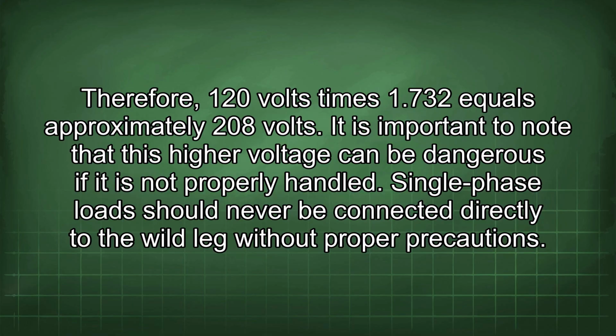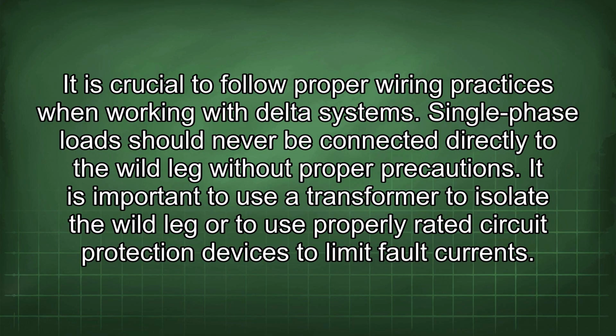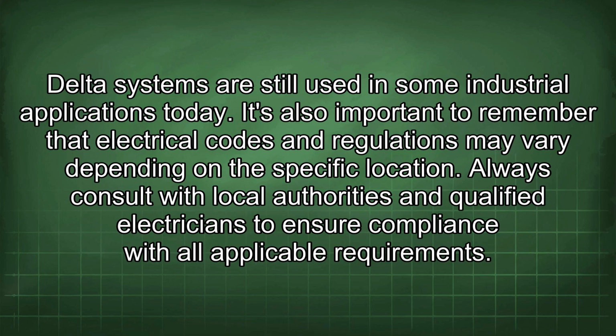It is important to note that this high voltage can be dangerous if it is not properly handled. Single-phase loads should never be connected directly to the wild leg without proper precautions. It is crucial to follow proper wiring practices when working with delta systems. It is important to use a transformer to isolate the wild leg or to use properly rated circuit protection devices to limit fault currents. Delta systems are still used in some industrial applications today.